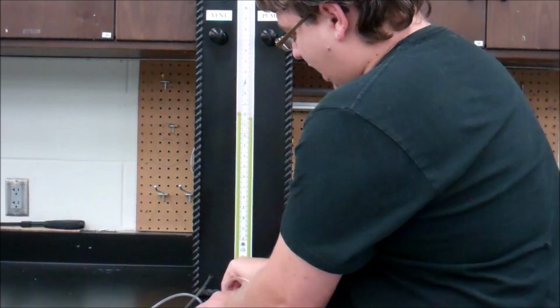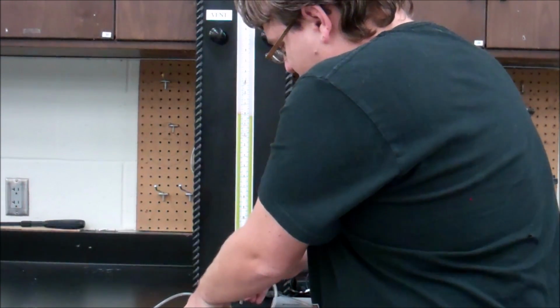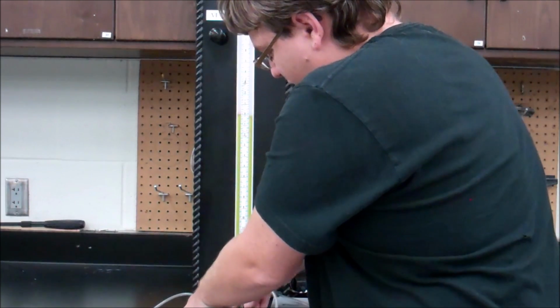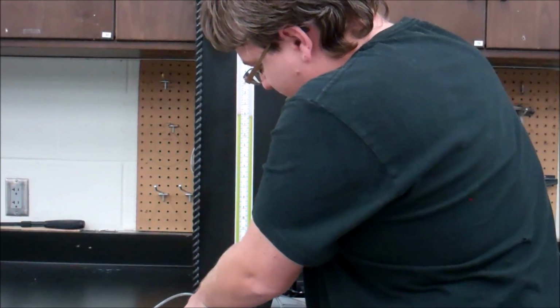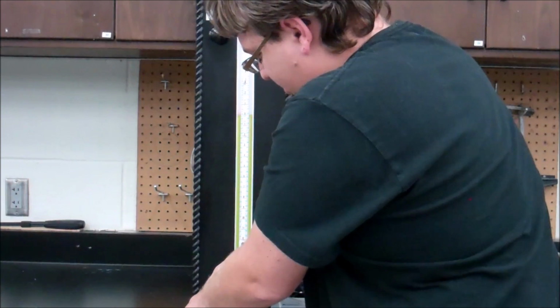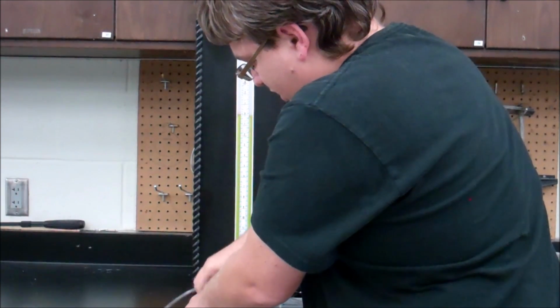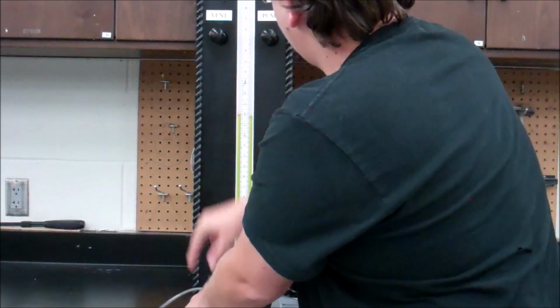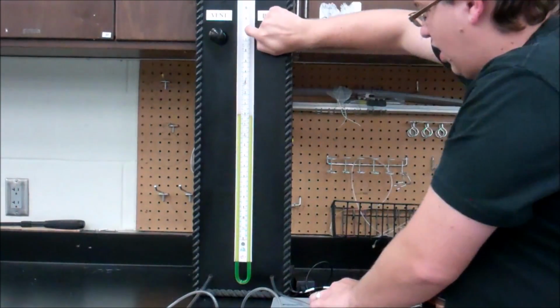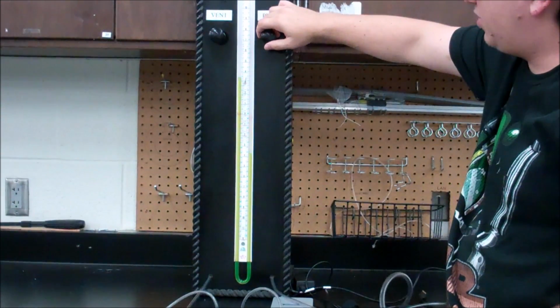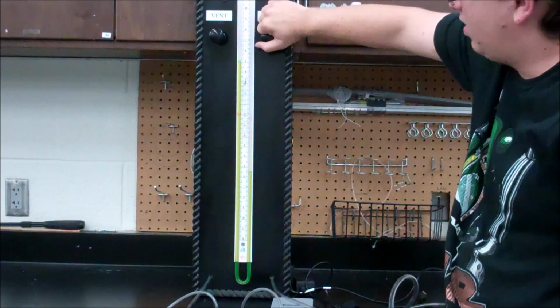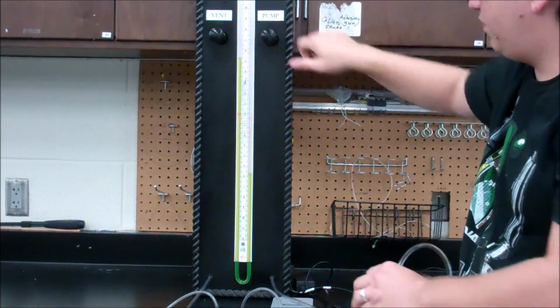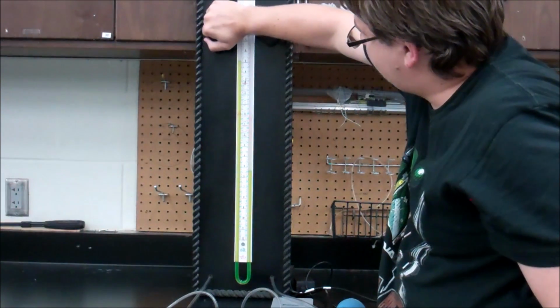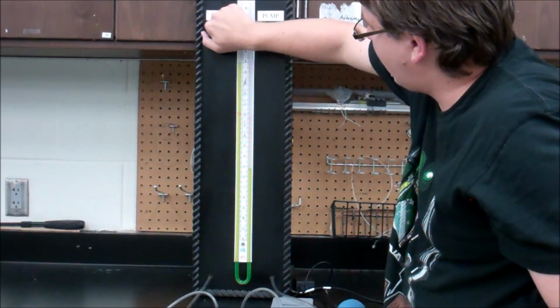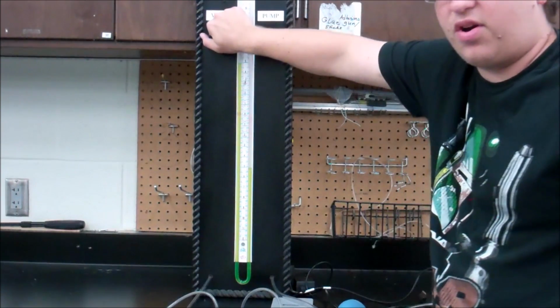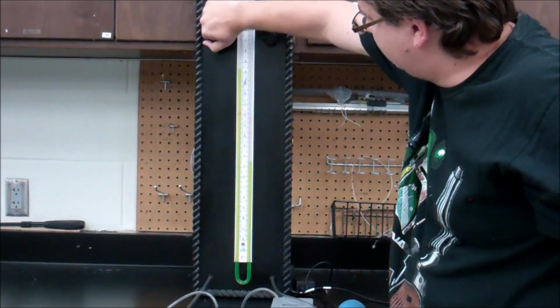Now, once you do the high side, you take the pressure transducer and switch both tubes from the high side of the pressure transducer to the low side of the pressure transducer, which is the right side. And then you're going to do it again. You're going to close your vent, open your pump a little bit, pump up to +5, -5, go past it a little bit, turn your pump off, vent slightly to get to 5 above and 5 below, which is 10 inches of water column, and then keep on venting.